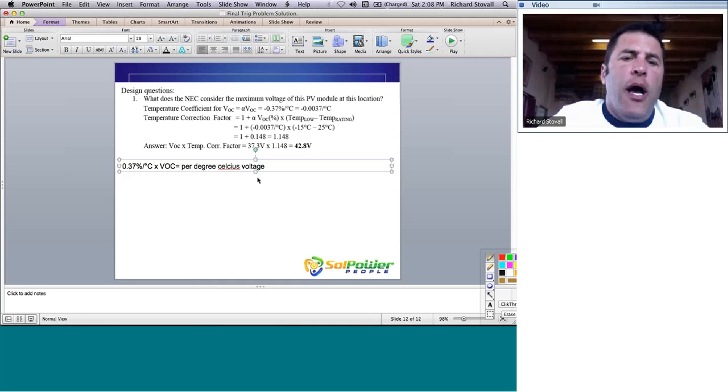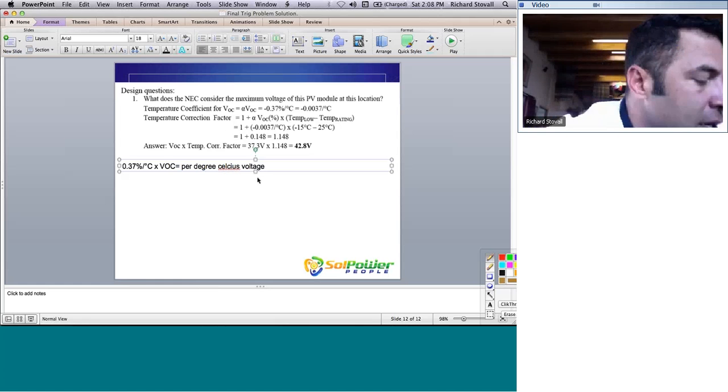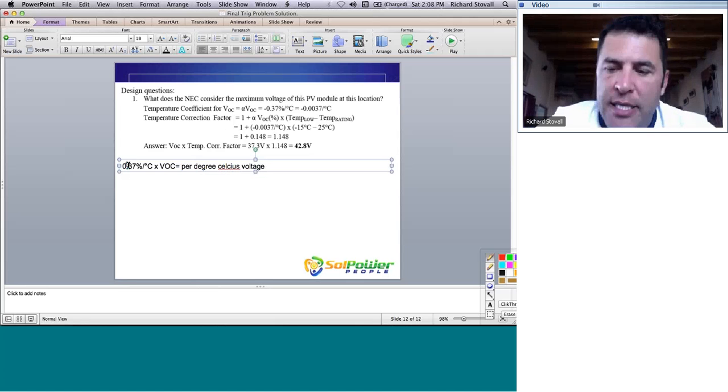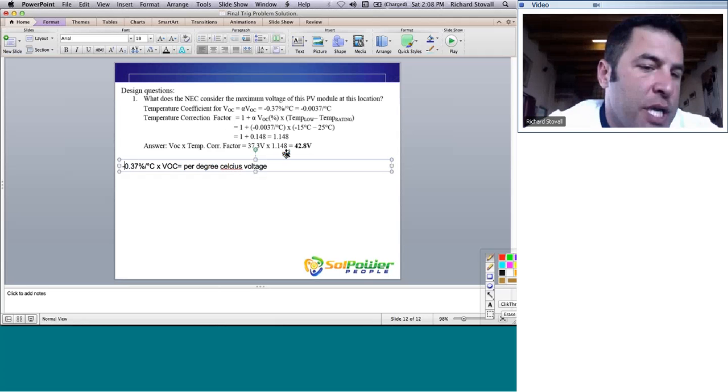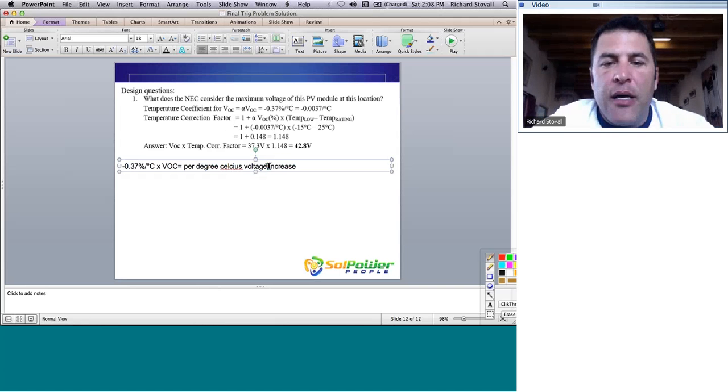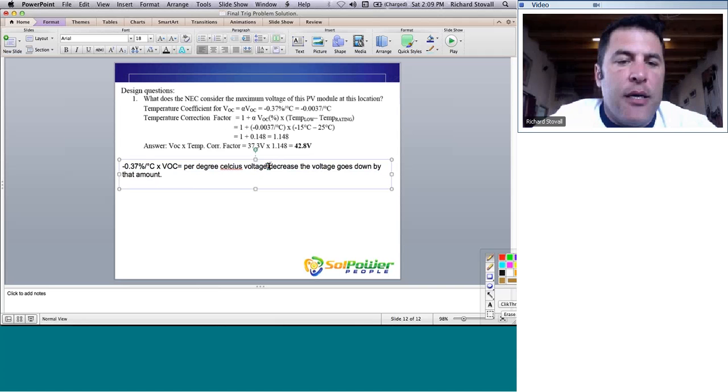Okay, so for this particular module, for every degree Celsius that it changes, it's actually a negative relationship. It's stated as negative 0.37% per degree Celsius times the VOC. Which means that for every degree Celsius increase, the voltage goes down by that amount.